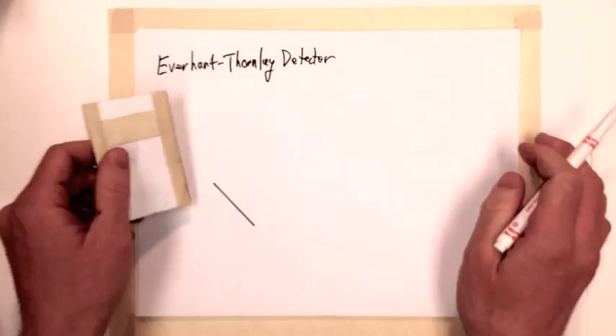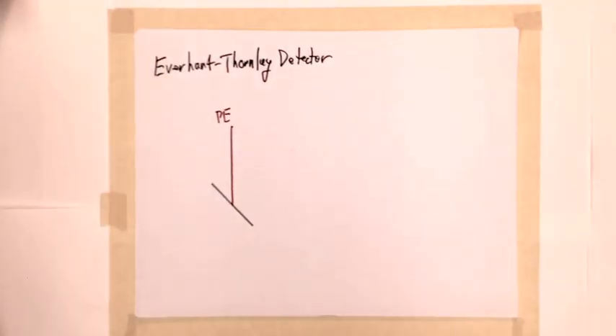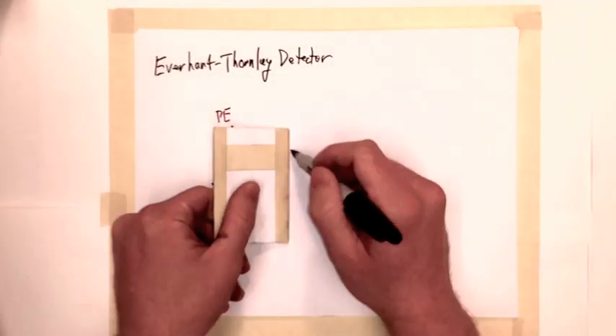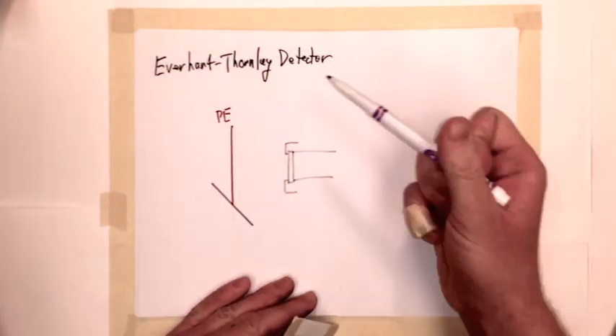Although the Everhart Thornley design is primarily used to detect secondary electrons due to their low energy, it will also detect any backscattered electrons propagating through the same solid angle. The Everhart Thornley detector uses a positive potential operating at approximately 300 volts to attract secondary electrons towards the detector.